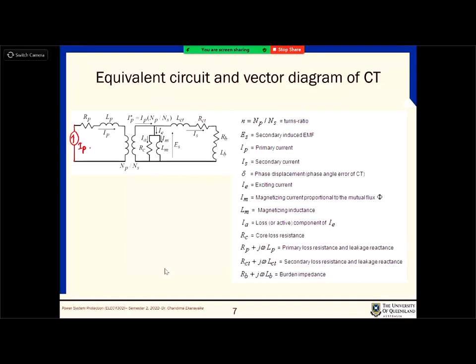And then, when we are studying CTs, it is also important to look at, sometimes, the equivalent circuit for calculations. So the transformer equivalent circuit is valid here, but the difference between the normal transformer and this equivalent circuit is, when we are doing the calculations, typically in a transformer you apply a primary voltage VP, right? Now, are we applying a voltage to the primary or a current? That is the main difference, right? Because it's a CT, instead of a primary voltage here, you need to put a current source, or current IP, right? In a calculation, a current IP is going through it. And then the rest of the circuit is the same as the normal transformer equivalent circuit.